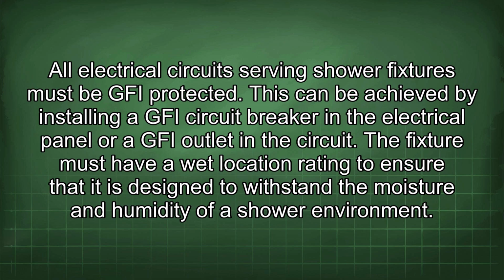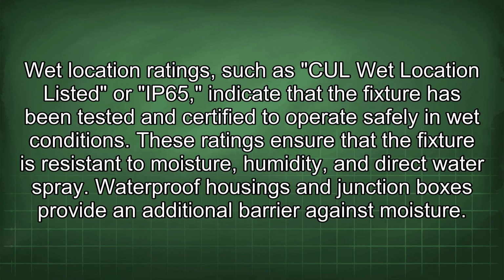This can be achieved by installing a GFI circuit breaker in the electrical panel or a GFI outlet in the circuit. The fixture must have a wet location rating to ensure that it is designed to withstand the moisture and humidity of a shower environment. Wet location ratings such as CUL wet location listed or IP65 indicate that the fixture has been tested and certified to operate safely in wet conditions. These ratings ensure that the fixture is resistant to moisture, humidity, and direct water spray.